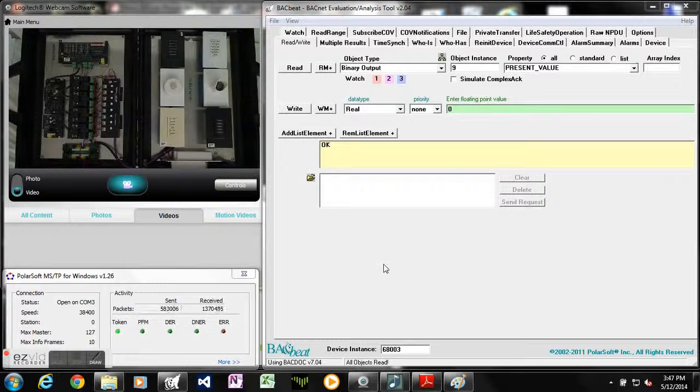Okay, next we're going to cover analog value objects, objects 1 through 32, AVs 1 through AV 32, and these correspond to the LEDs on the stations, the various LED modes. So if there's programming on the controller for local programming, the pilots are controlled via the controller and they just correspond to the output that they're set up to control.